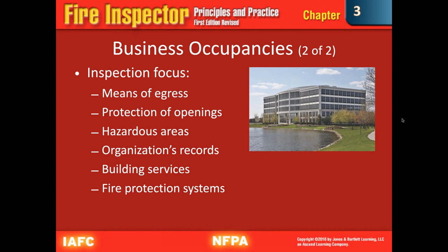Typically, large number of occupants during the business day and limited occupants during non-business hours. The buildings that you're going to see on these are your 9-to-5 buildings. When they close up for the day, if there's anybody there, it's usually just a cleaner or a security guard and that kind of thing. There's no customers. Most of the workforce is gone. Inspection focuses on means of egress, protection of openings, hazardous areas, protection of organizations' records, and building services such as waste disposal and the utilization of shafts, chases, and fire protection systems.